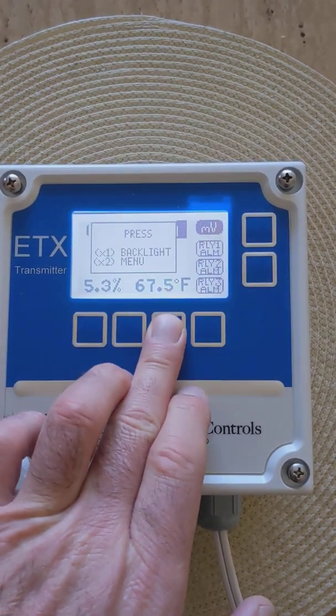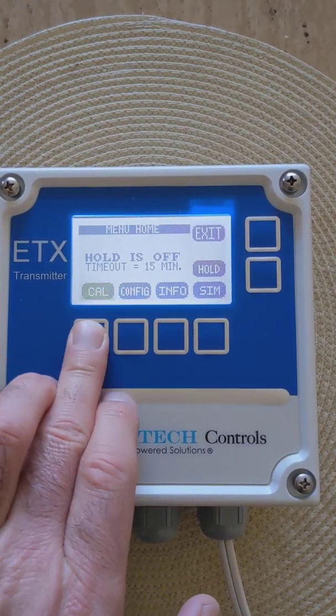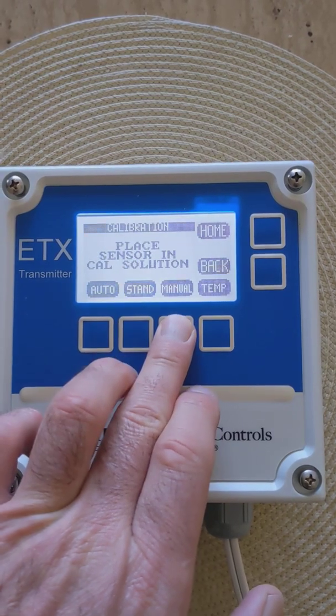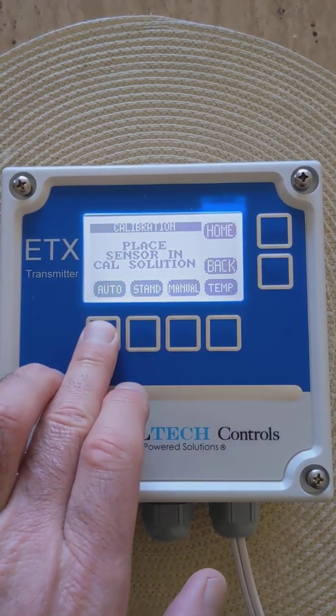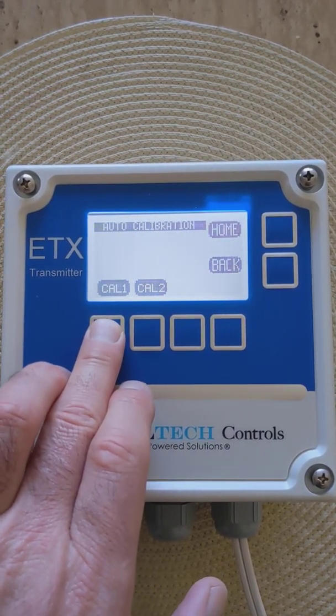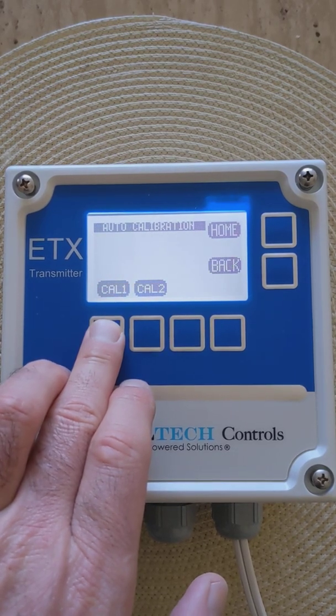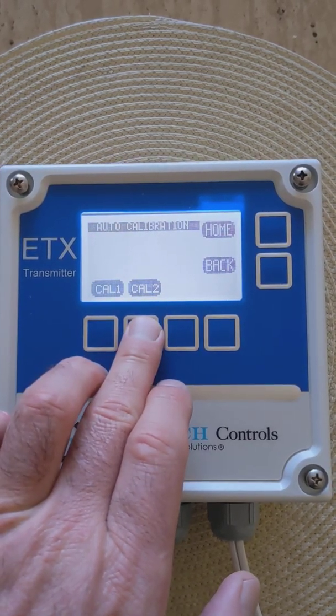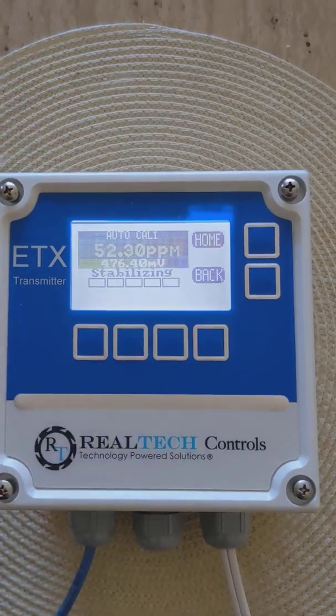I'm going to hit the calibration. It's not a new sensor. I want to do automatic calibration. That's for a 2-point. And it says Cal 1, which is your 0, and Cal 2, which will be your slope. So I'm going to hit Cal 1.